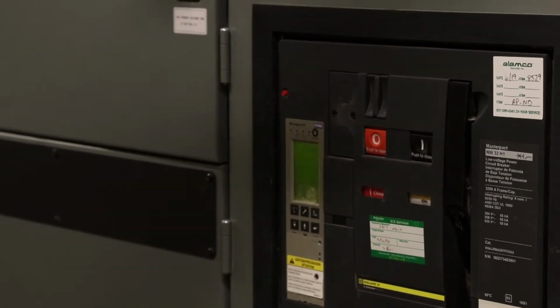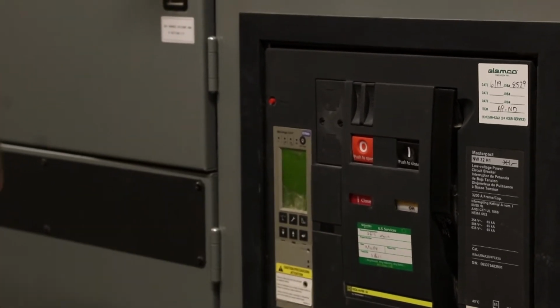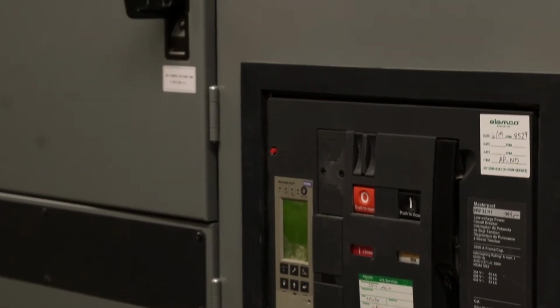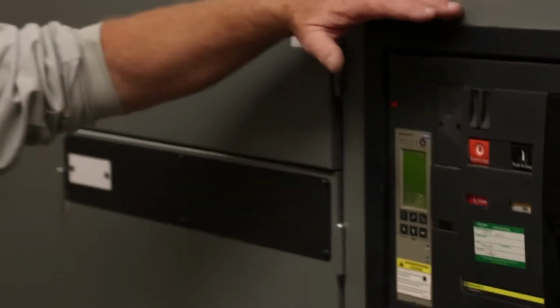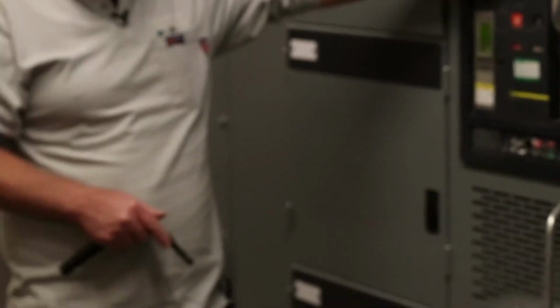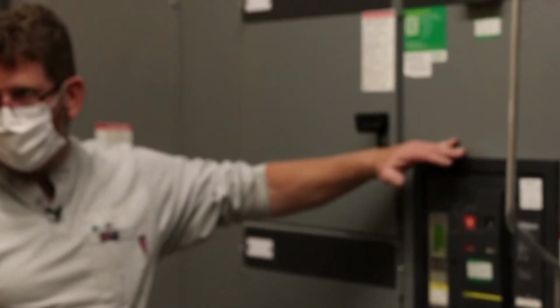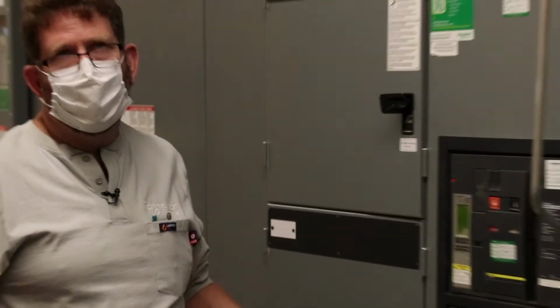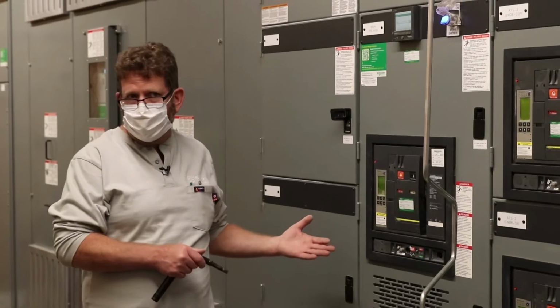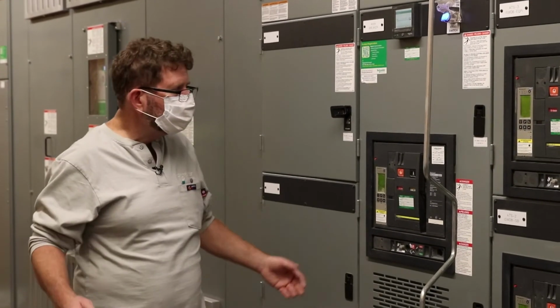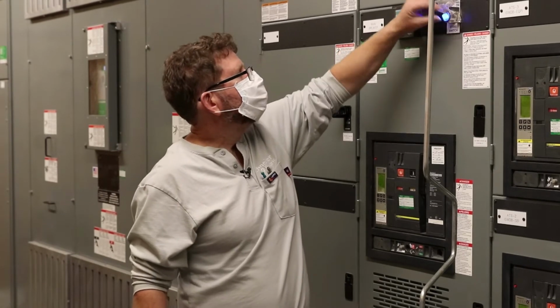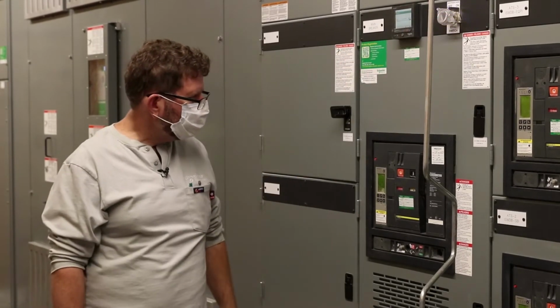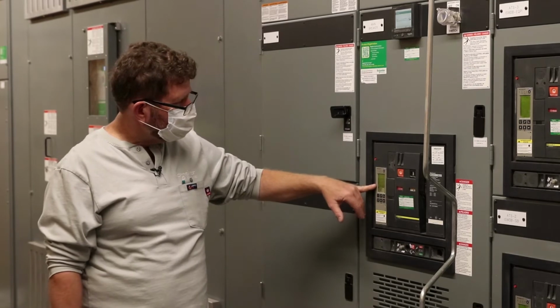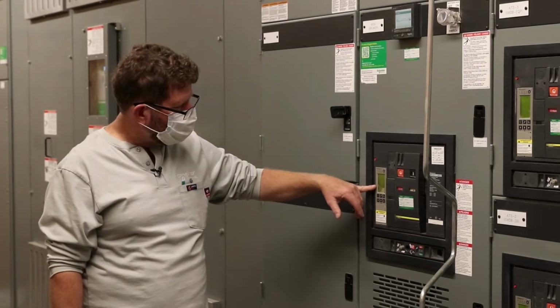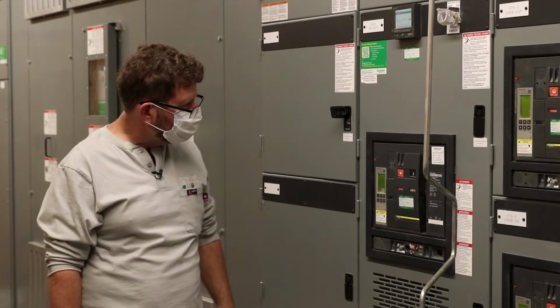The only risk you have when you take this to ERMS is now you may not have the coordination that you would normally expect operationally, because again your instantaneous setting was 48,000 before. Now it's 6,400. If you're starting a very large motor while you're in ERMS, you run the risk of tripping the breaker. Light goes out, and then it's going to come back to normal, and it's just not going to say ERMS any longer.